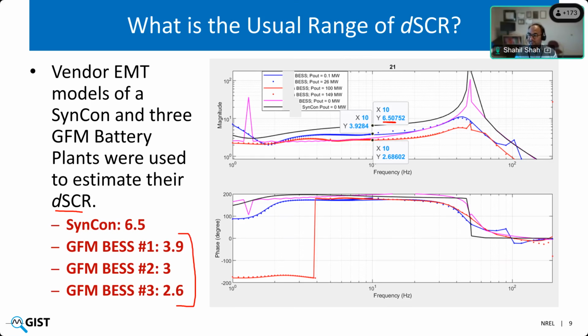Deepak, do you have anything to add? That's the idea behind using these functions: reactive power versus voltage, active power versus angle, both in this form or in the inverse form, allow for a little bit of operating point independence. Now, if we use more of the impedance related functionality, then there is more operating point dependency that comes into play when we're looking at the impedance or admittance. But the reason behind using these functions here is that the operating point independent nature actually makes it very easy to carry out the scan.